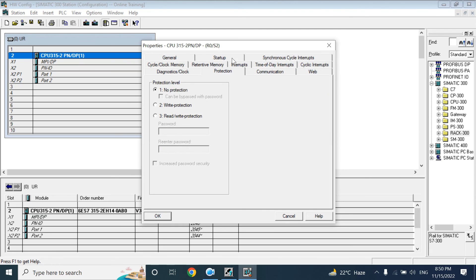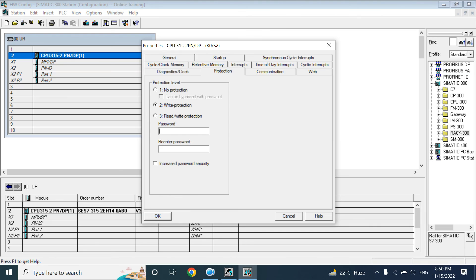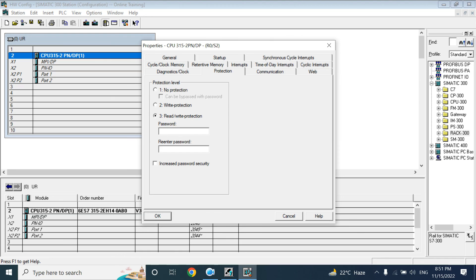Here there is another option that is called the protection level. By default it is no protection, means no need for password. If you select the write protection, if you give here the password, it needs password to download the project to PLC. But for going online, for monitoring, no need for password. For downloading it needs password. But if you choose 3, then your password is needed all the time to read, monitor or download. I will keep it as no protection.